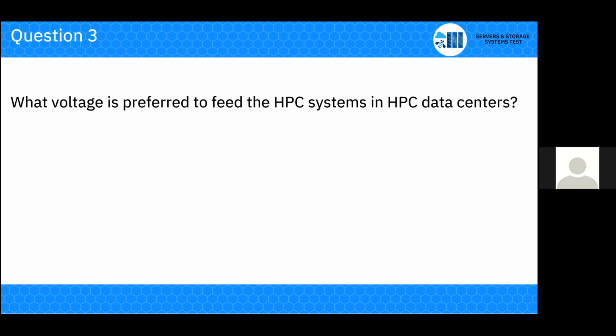Right. Good point, David, because I know once you go above 250 volts, you can no longer use the IEC 320 connectors, C13, 14, 19, 20, and it does make it a little more challenging to find the right connector, and the power supply design with the capacitors and inductors has to be sized appropriately. Again, once you go above 250. So last but not least, Ethan.